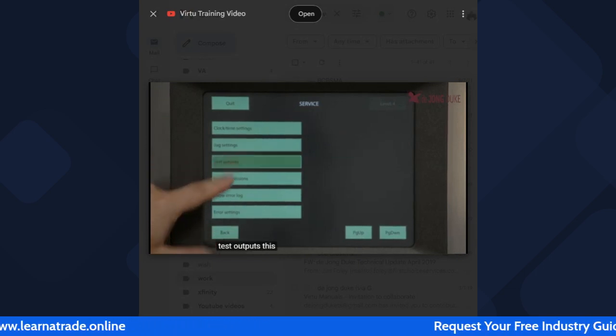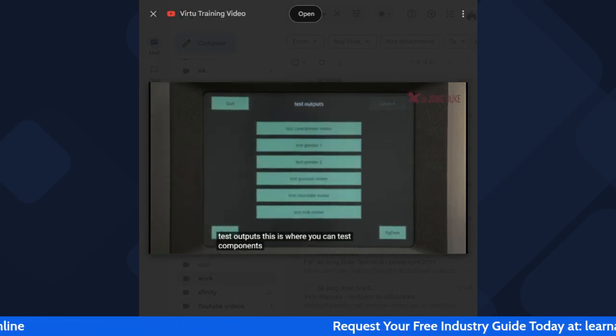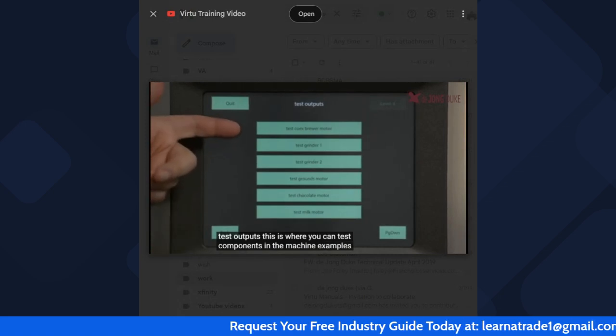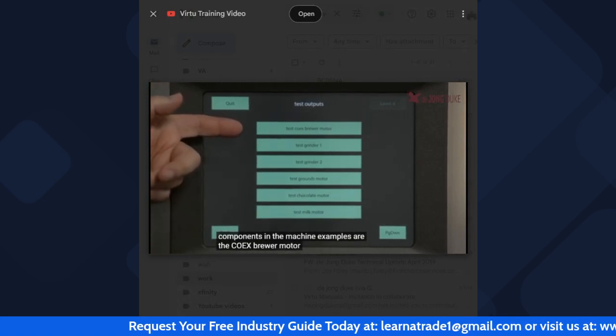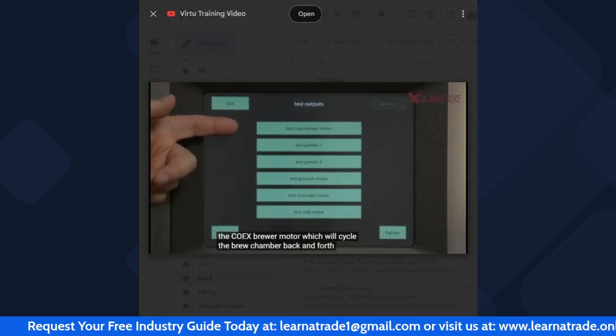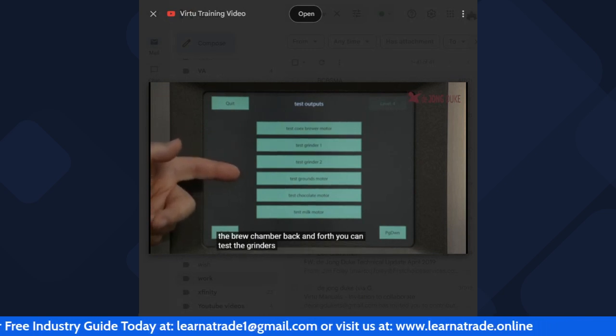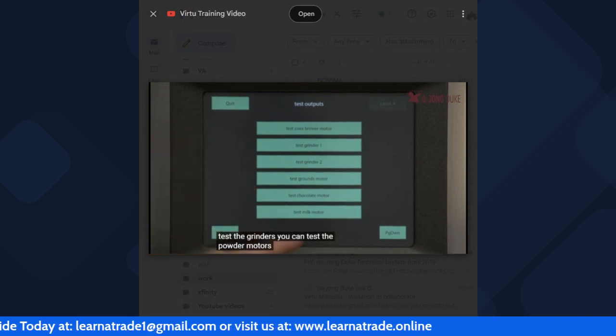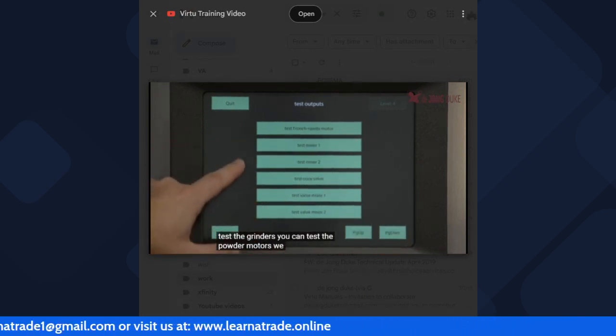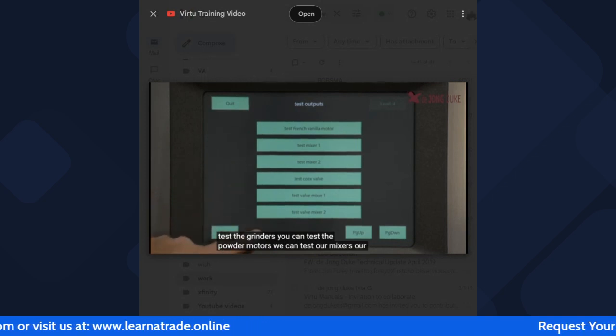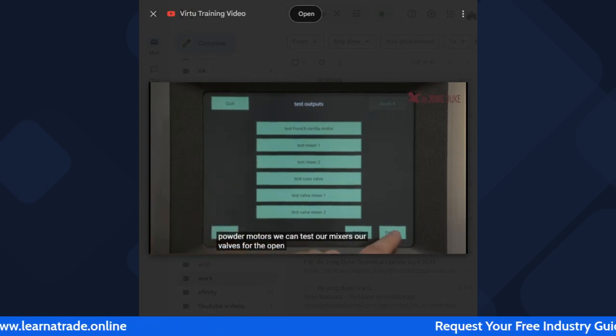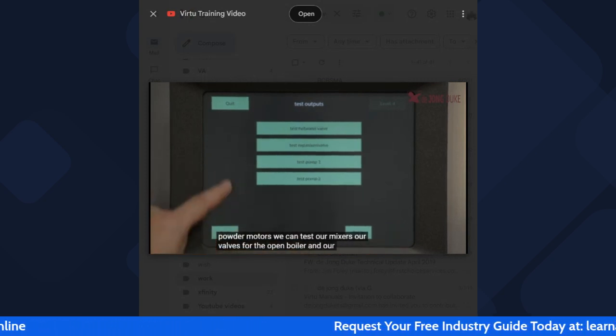Test outputs. This is where you can test components in the machine. Examples are the COEX brewer motor, which cycles the brew chamber back and forth. You can test the grinders, the powder motors, our mixers, the valves for the open boiler, and our pumps.